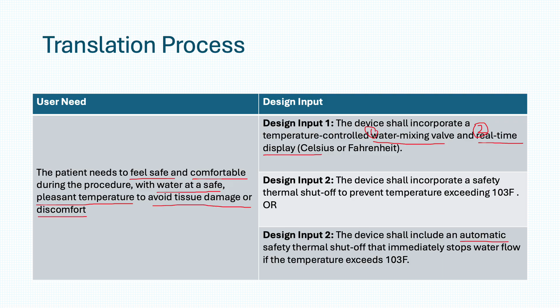It's simple, right? If your initial requirements or design inputs are vague, incomplete, or just plain wrong, then the final device will be wrong too. No way around it. The quality of the entire project depends on getting this step right. Be mindful that this is where many design issues occur: incomplete or ambiguous design inputs. Therefore, it's critical to have a defined process to ensure all design inputs are verifiable. User needs and design inputs can be categorized into different sections such as performance, safety, usability, regulatory, incorporating all sources of information you have, including engineering design or engineering standards. Therefore, you turn that garbage in, garbage out concept into quality in, quality out, good in, good out.